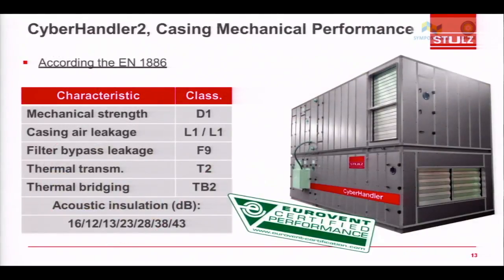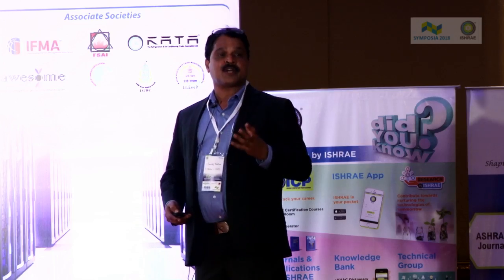Again, when you do an air handling unit, you have to give importance to all these parameters: mechanical strength, casing air leakage, filter bypass leakage, because a small leakage will lose you PUE, and in turn you will lose money. So if you want to save money, please check thermal bridging and thermal transmission. In the majority of places, leakages have to be completely controlled in air handling units: filter bypass leakage, casing air leakage. So go to the AHU manufacturer who can offer these tests and say your product is really foolproof in this line.